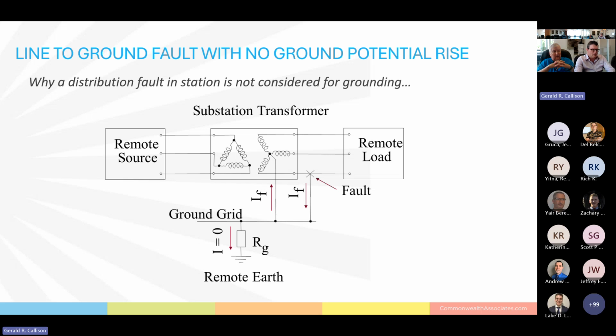But instead of going through the grid to soil interface and creating a V equals IR ground potential rise, it stays in the ground grid largely and goes through the ground grid from the fault location to the location where this transformer neutral is grounded. And then it goes through those ground leads into the transformer neutral back to the fault. So basically, it is a circulating current, and we do not consider this for grounding, aside from a few very specialized situations.